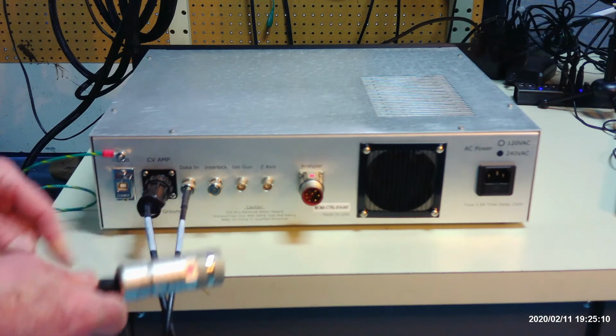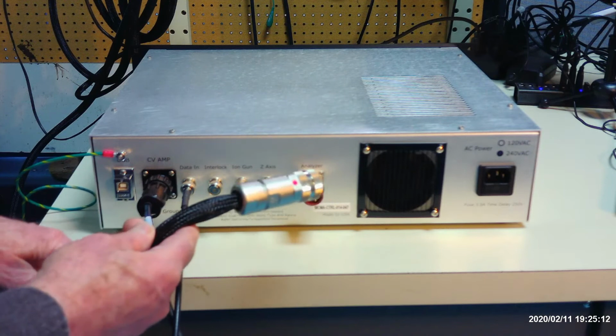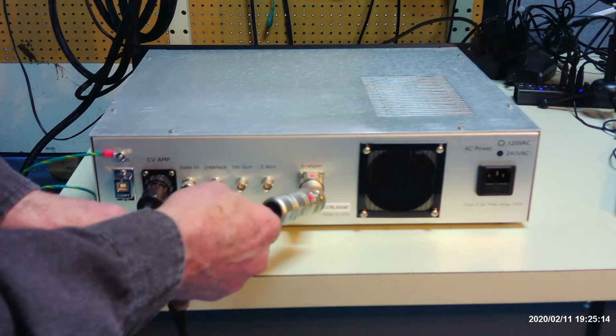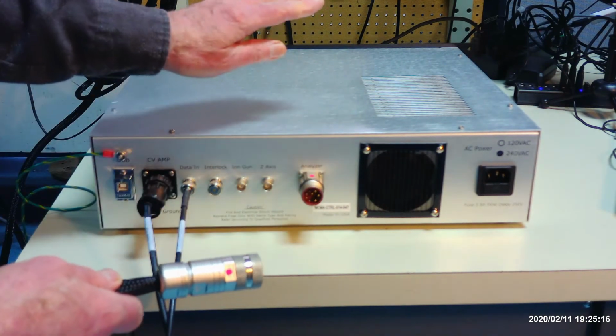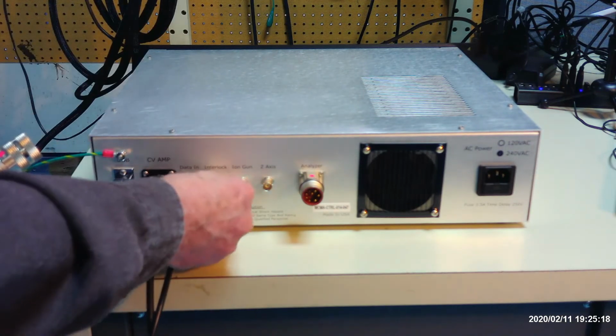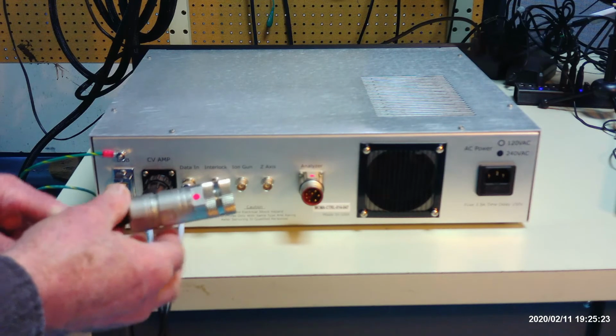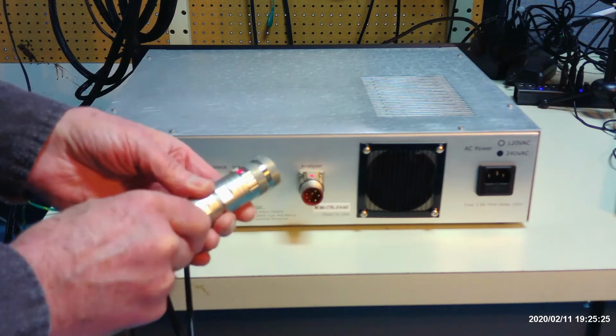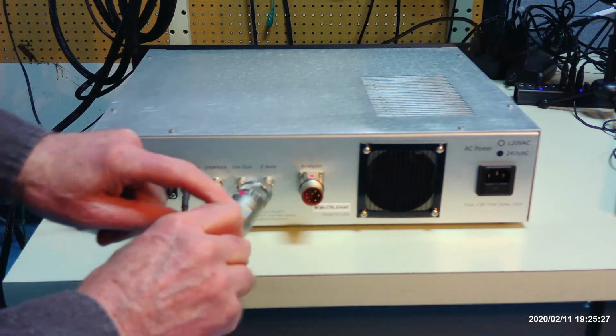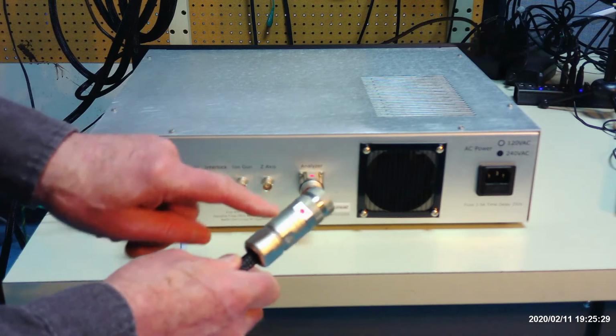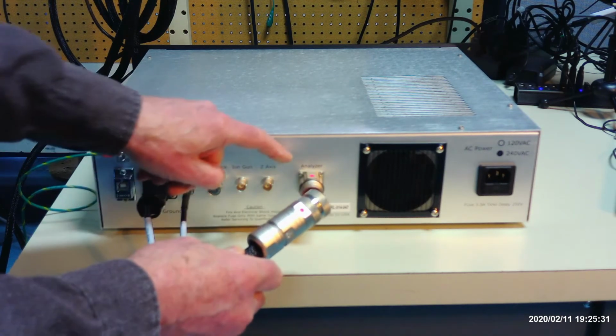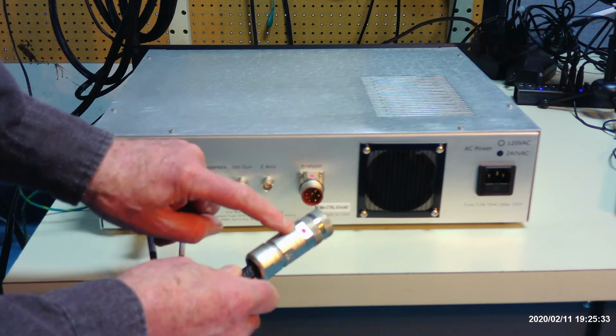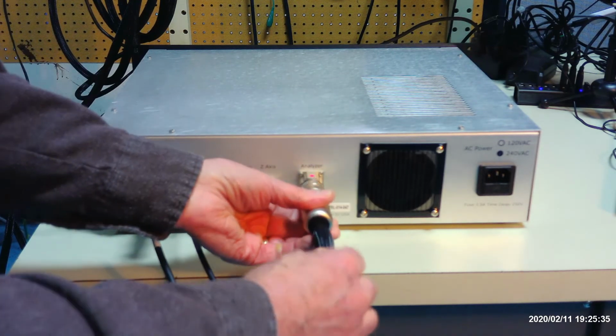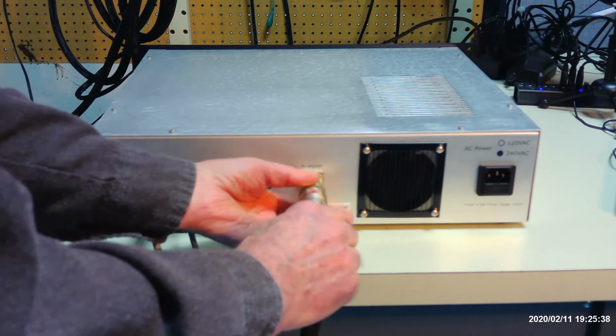By the way, our controller is designed so that if this cable is not connected to the analyzer, then all the high voltages are disabled. If the vacuum interlock is not connected, all high voltages are disabled. So that's a safety feature. Now, this connector has a couple different flat spots on it, so we always mark it with a little marker here to guide you on which direction it needs to go. So we'll position it like this so those dots line up.